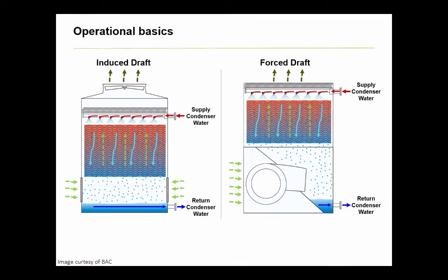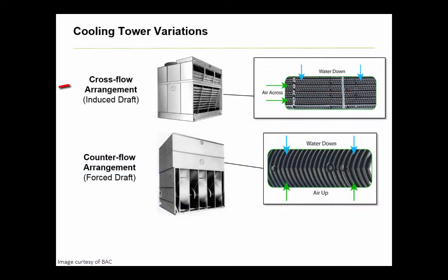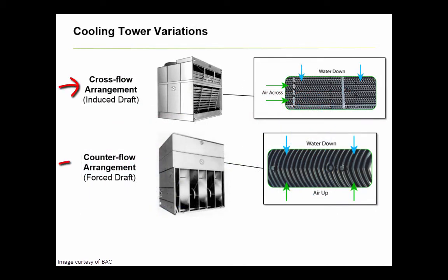To go just one technical layer deeper with these two tower types, there are a few important variations to mention. First, they can operate in a cross flow or counter flow arrangement, meaning the air moves perpendicular to the falling water in a cross flow arrangement, or in opposite directions with a counter flow arrangement. There are various reasons why each is employed.